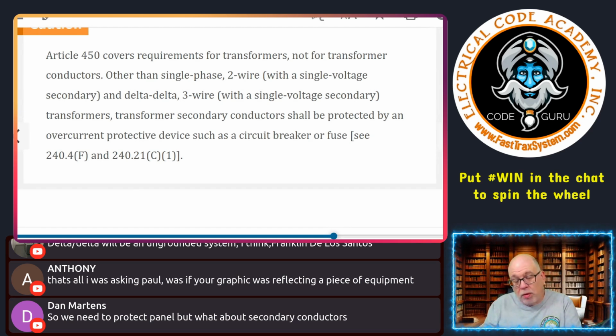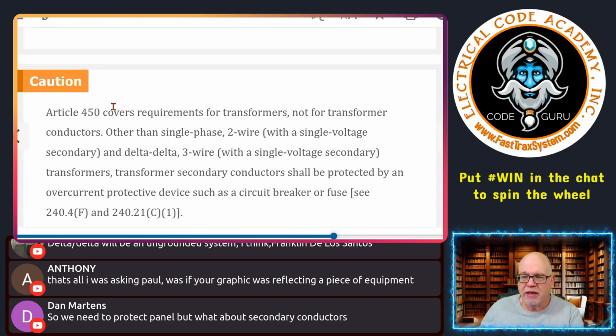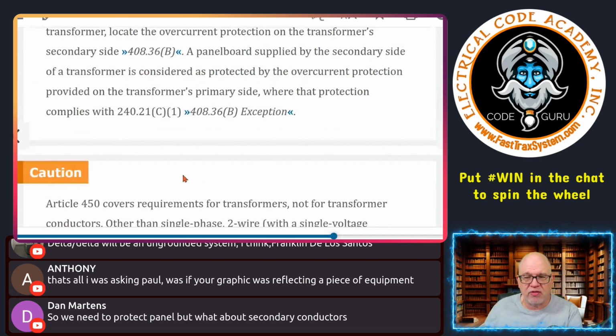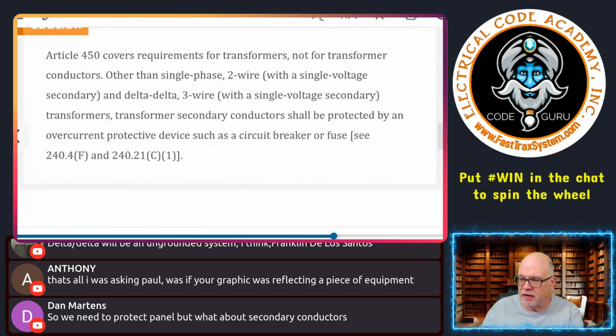Now, what we were talking about is a panel board that's supplied from a transformer. Typically, you're going to go into an overcurrent protective device. But there are applications where all of that is considered protected from the primary side if you meet all of the rules that are involved in 240.21(C)(1), which is the secondary conductor rules, that type of scenario. Okay, we'll look at that a little deeper as we get into some graphics.